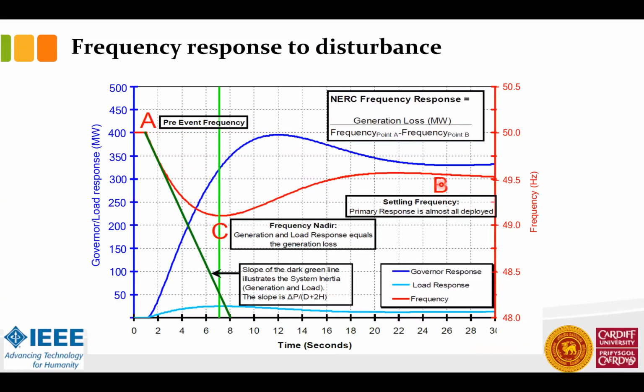More importantly, if there is an event such as large generation tripping from the network or a large load connected to the network, you are going to see a dip in the frequency. So what you are seeing here, the red one, at point A you lost a generator, the frequency goes down and it is stabilized by the governors of large generators and brought back to a value, not 50 hertz, but slightly lower, and later you can rectify that. That is what normally happens.